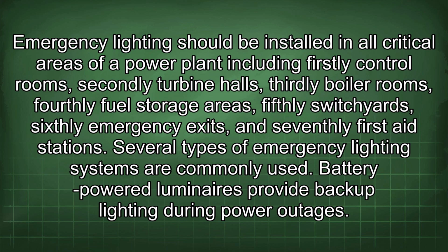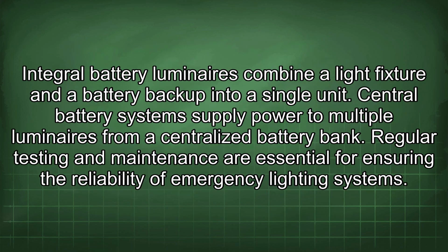Several types of emergency lighting systems are commonly used. Battery-powered luminaires provide backup lighting during power outages. Integral battery luminaires combine a light fixture and a battery backup into a single unit. Central battery systems supply power to multiple luminaires from a centralized battery bank.